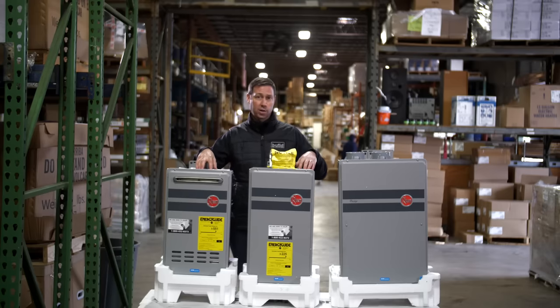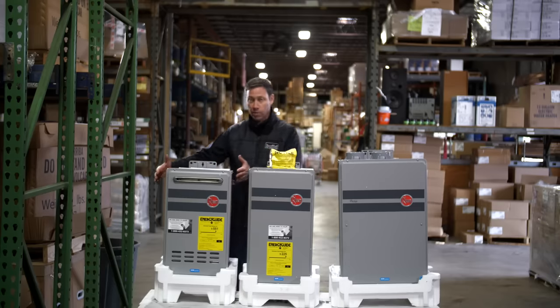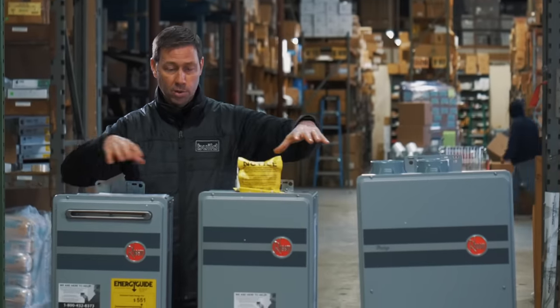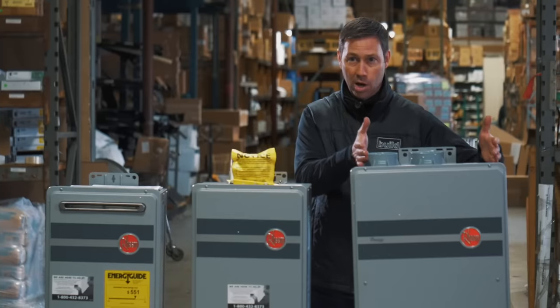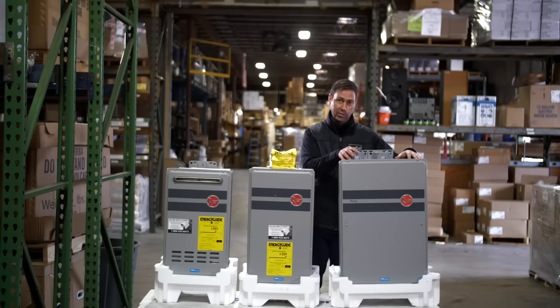There are really two types of tankless water heaters: non-condensing and condensing. These two smaller units right here are traditional models — they're non-condensing. Typically, across all the manufacturers, these are roughly 0.8 EF rating. The condensing models are about 10% more efficient with a 0.9 EF rating.